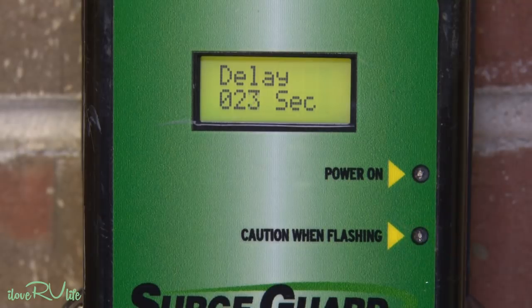The second thing I want to share, which is a tremendous benefit of this device, is notice there's a delay going on, roughly about a 2-minute delay. Why is that important? If the power at your camper goes off and on during the summer while your air conditioning is running, losing power will cause this to shut off. When the power comes back, whether 5 seconds or 5 hours later, what you really have to worry about are those intermediate power outages, off and on, off and on during a lightning storm. This will shut off for 2 minutes before putting power back into your camper.